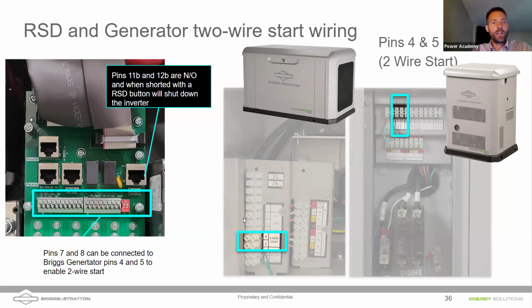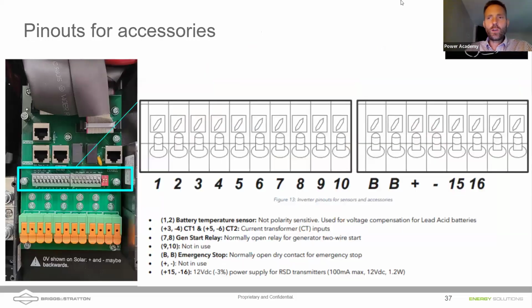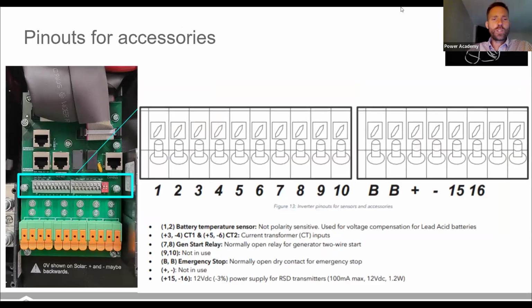Pins 7 and 8 on the Sol-Ark are a normally open, dry contact. In the event that it wants the generator to start, it would close those contacts, and that would automatically start up that generator and then start charging those batteries after that signal is qualified. So here are the other ports on the comms board of the Sol-Ark 15K. Temperature sensors you're not going to use unless you're using older lead acid batteries, which are really a lot less common now. But if you have an existing install with lead acid batteries, you could use that temperature compensation sensor, and that would allow the Sol-Ark inverter to do a better job at getting your state of charge.